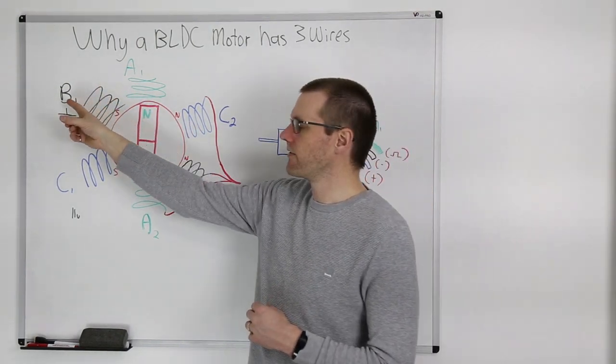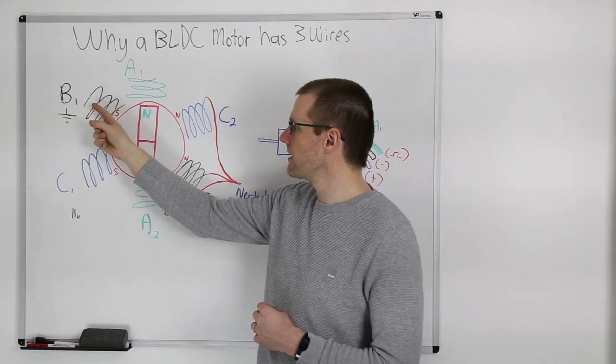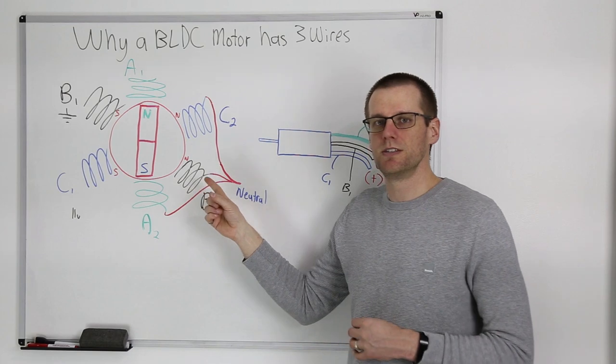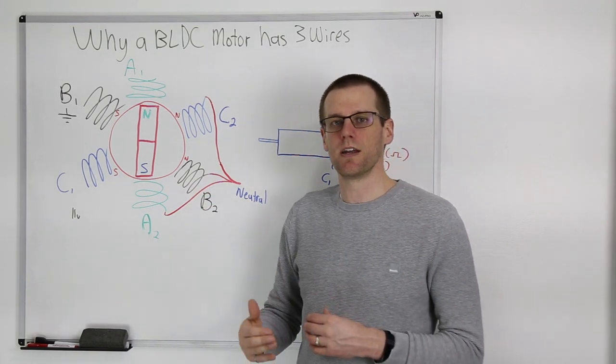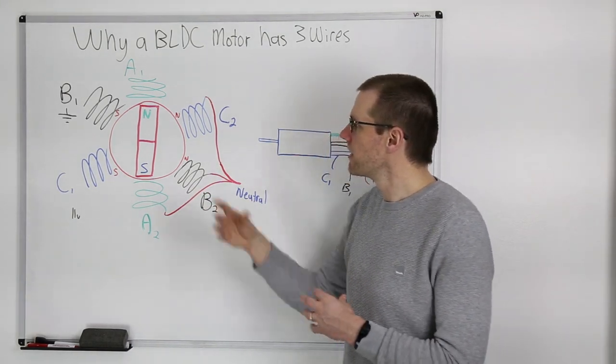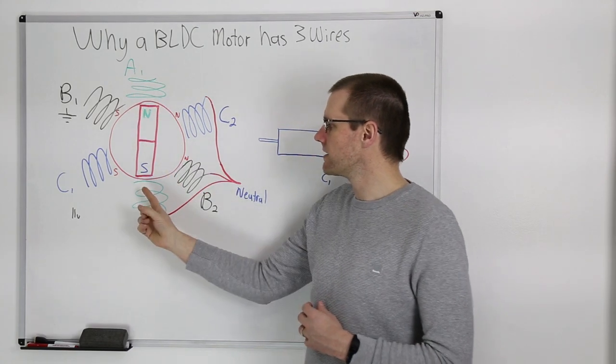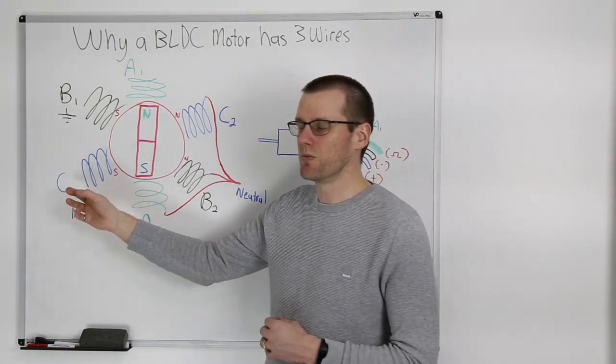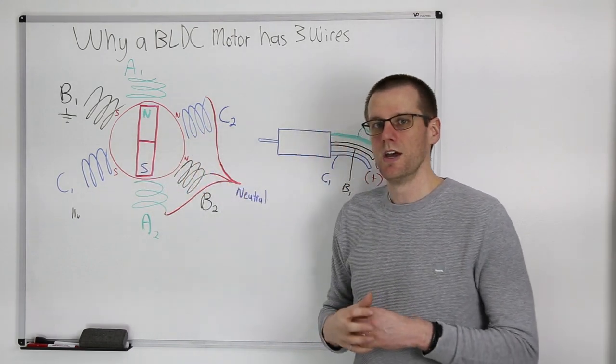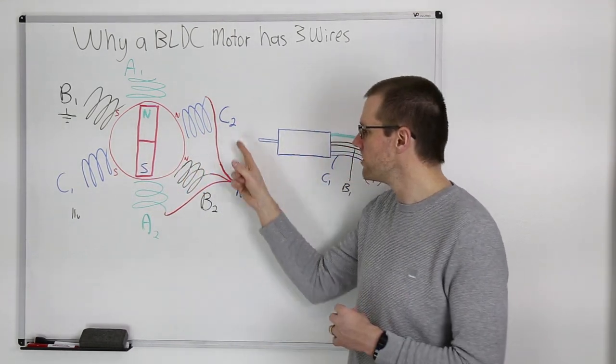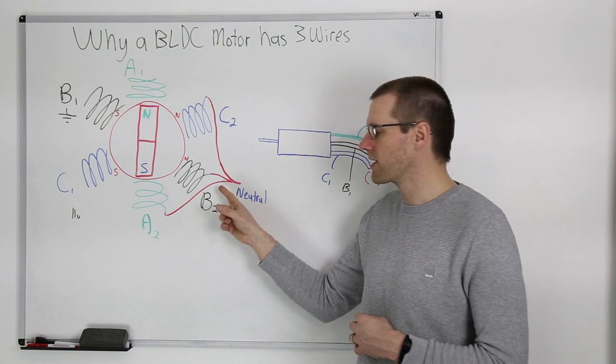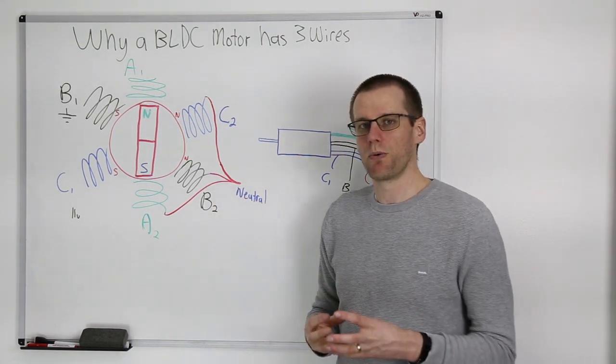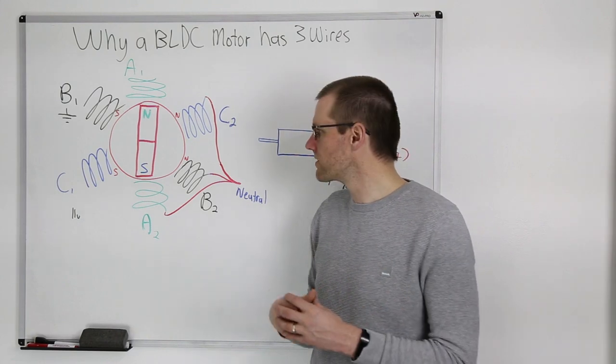So let's take a look at B1 for example. We have a winding that is ran here and it is connected to B2, which is exactly on the opposite side of the motor. Same thing for A1, it is going to be connected to A2 on the opposite side of the motor. And same thing with C1 connected to C2 here. Now, if you notice all of the twos, A2, B2, and C2 are connected by this wire that forms a neutral point within this motor. And that is quite important.